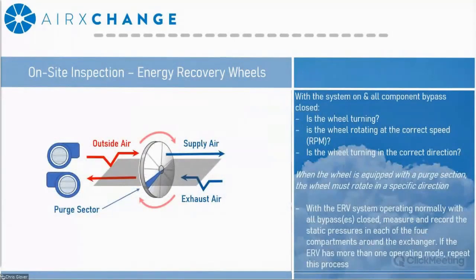So for the second part of the inspection, you're going to want to turn the system on. First thing you're going to want to do is determine if the wheel's turning. Now, this may seem trivial, but the first thing you're going to want to do is go to the actual unit itself and not rely on a building management system, because I've seen a lot of false positives in the past. If you have the capability to determine what the RPM of the wheel is, a lot of energy recovery wheels have been equipped with a VFD, and over time those system settings may not actually be what the equipment manufacturer recommends. So take note of that if you can.